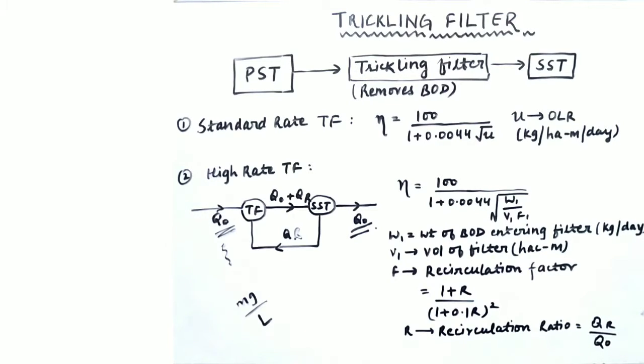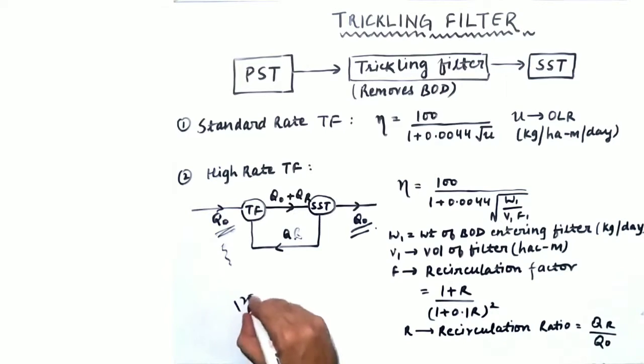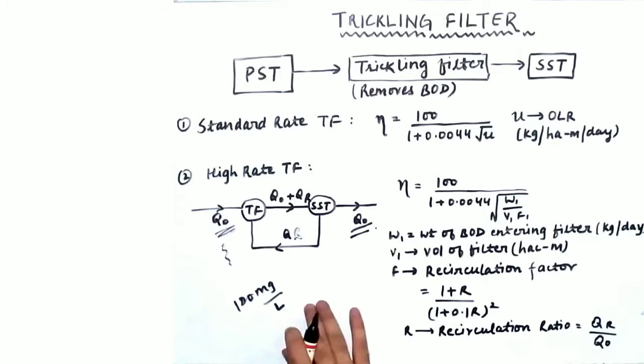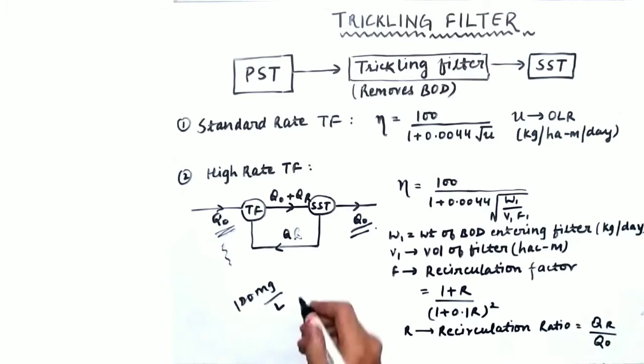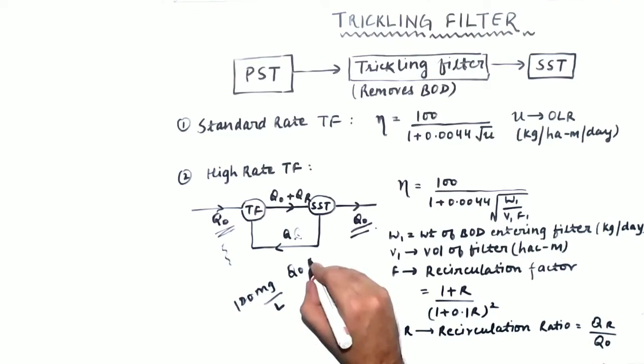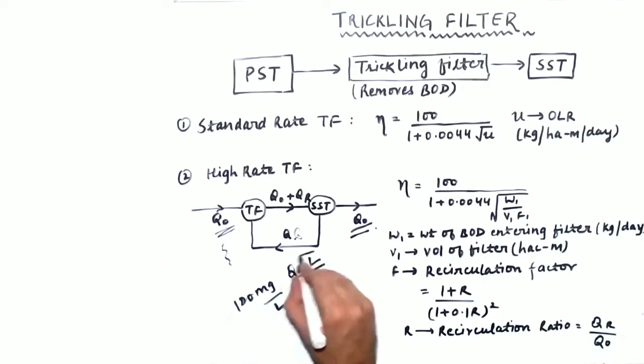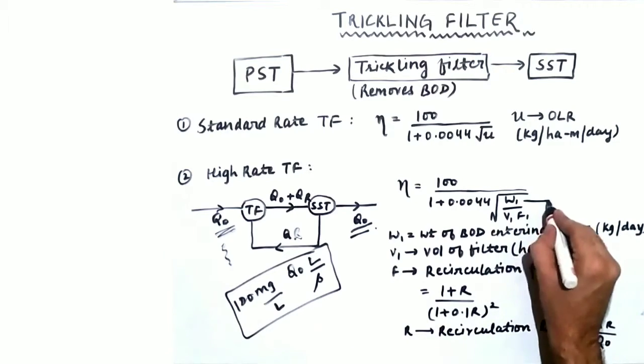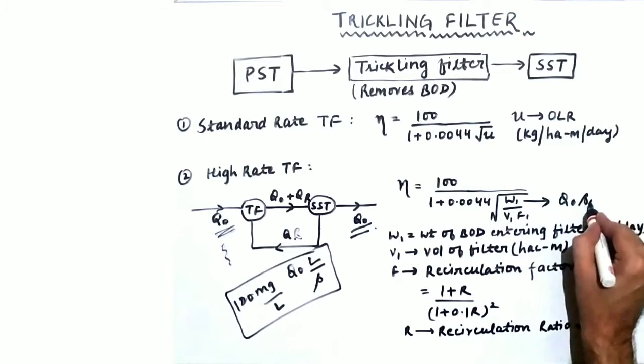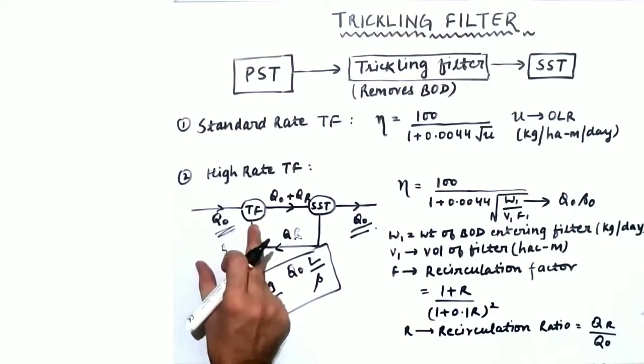W1 is calculated as Q0 multiplied by S0, where S0 is the BOD of the sewage entering the trickling filter in milligram per liter. The BOD concentration is always given in milligram per liter, and multiplying by the discharge Q0 gives the organic load W1 in kilogram per day. S0 is the BOD entering the trickling filter.